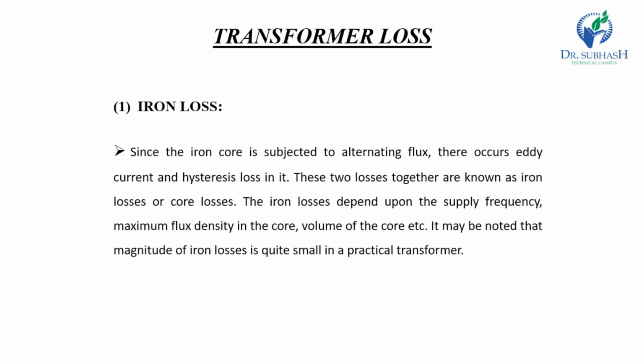We know that iron losses in a transformer do not change with the load. It is a constant type of loss, and iron losses depend on the frequency. When the frequency is increased in any transformer, the iron losses will increase, because hysteresis losses and eddy current losses are both proportional to the frequency, and if the frequency increases, the eddy current and hysteresis losses will increase, and at that time the iron loss will increase.